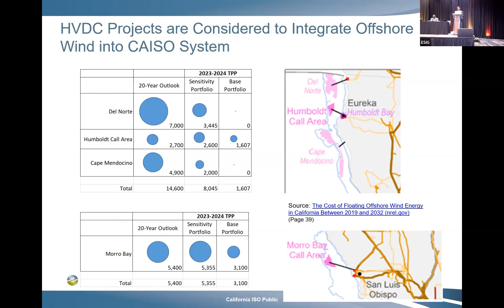In Central California, HVDC is being considered at a high level either as a line from the Diablo area to Northern California delivering power to Moss Landing, which eventually serves the Bay Area load center, or as a DC line delivering power from the Central Coast Diablo area to Southern California, the LA Basin and so on, if the total offshore generation volume, combined with nuclear, exceeds the capacity of the existing 500 kV system in the area.